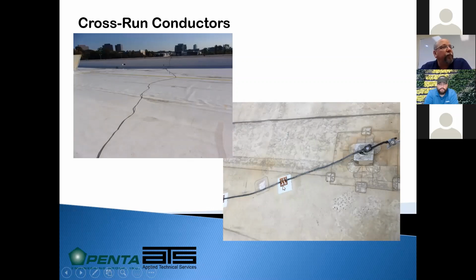So if you're doing a re-roof and you want to reinstall a lightning protection system or install a new system, be careful when you're getting bids, because a lot of lightning protection contractors just automatically exclude the sacrificial pads, and that can add up to a sizable job by a roofing contractor. Some of these rooftop systems where they have to be adhered every 3 feet can be hundreds of locations, and those sacrificial pads, I've seen pricing between $10,000 and $50,000 for the roofer just to install those sacrificial pads, depending on the size of the roof.